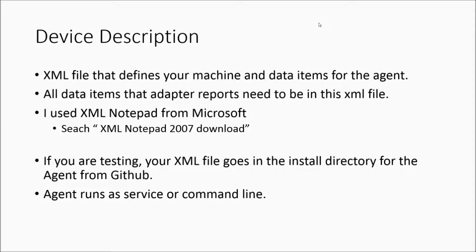The other part that's included in the GitHub, there is a definition file, an XML definition for your machine that is needed by the agent. So that knows what data could be coming on the SHDR stream from your adapter. All of the tags that we implement in the 1200 PLC will need to be part of that XML file. And again, I included a sample one with the sample tags that I have loaded.